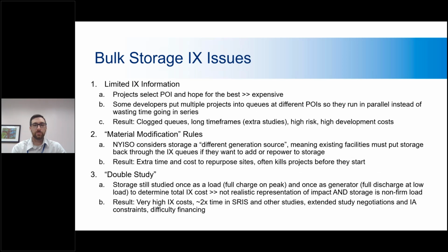A third issue we have is what I term the double study issue, where a lot of utilities and the NYISO are still operating under this single hour, worst-case-scenario storage interconnection study process, where storage is studied as a load once, assuming it's fully charging at peak times to see what the interconnection cost would be, and then doing another separate study to figure out what would happen if the storage is acting as a generator, injecting its full amount at low load times.